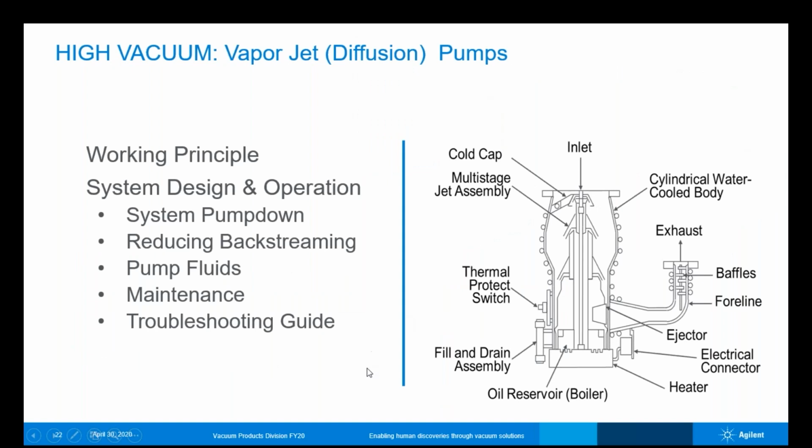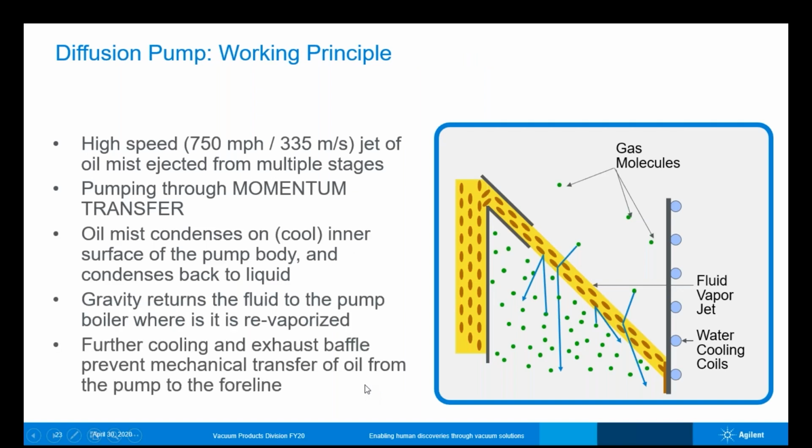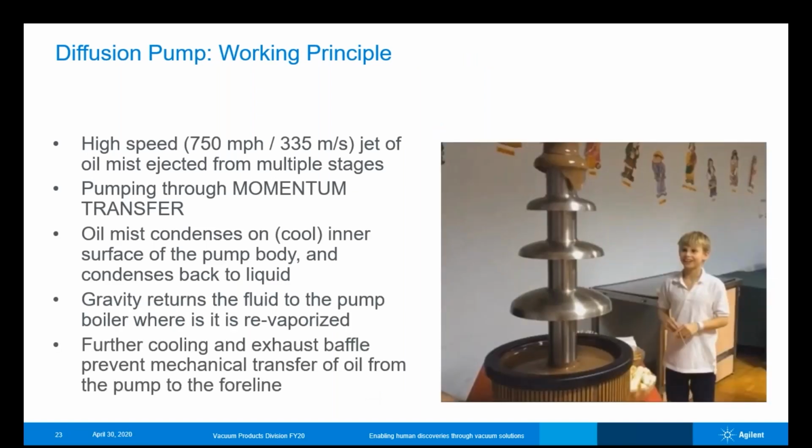So let's talk about these in some detail. They're the most common high vacuum pump that we're going to see in industrial applications. Let's go through some of the different aspects, and in particular we're going to talk about maintenance and troubleshooting once we get through how this pump actually works. As I said, the pumping mechanism is largely thought to be through momentum transfer.